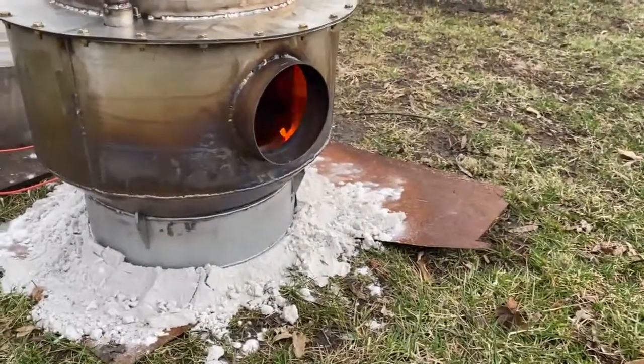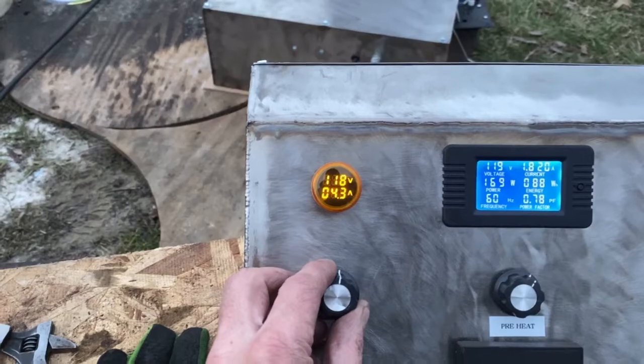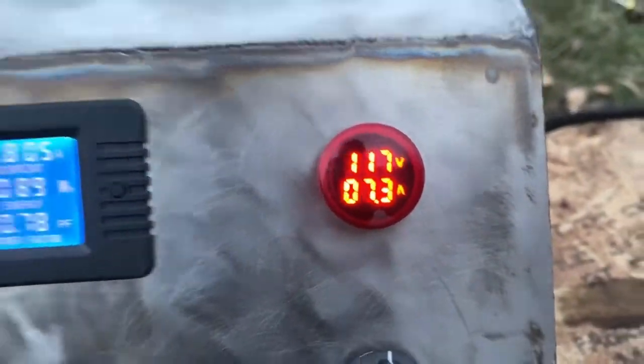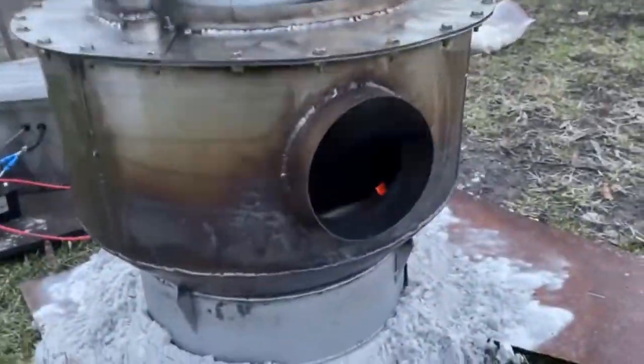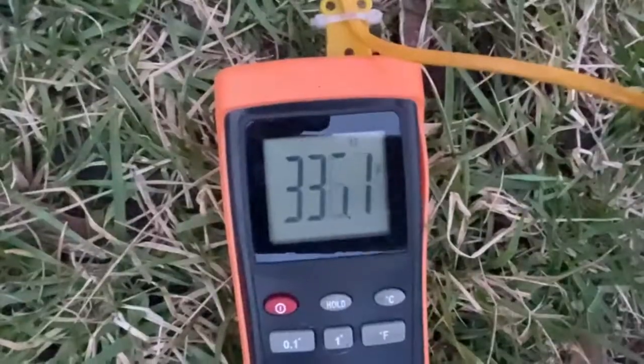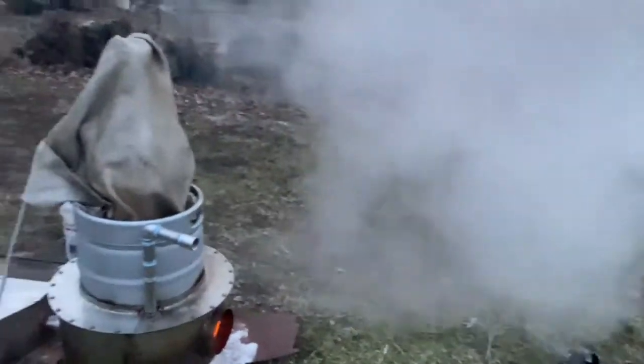It seems like a little too much fuel. Let's turn that down. Let's turn this blower back up to 5 amps where we were before. Keep that at 5 amps, 7.3 amps on the fuel. Getting steamed out. We're making about 300-something degrees steam.